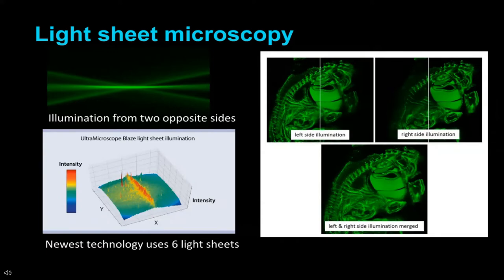Some light sheet microscopes also have software that actually adjusts the light sheet and imaging so that one field of view is made up of many different images, ensuring the light sheet is as focused as possible on that field of view.